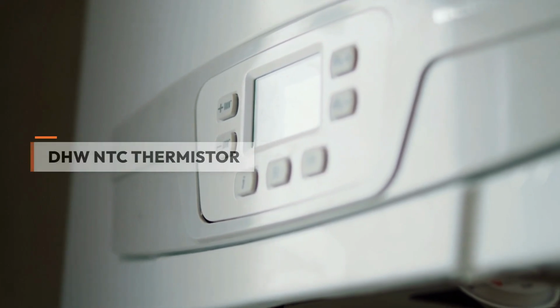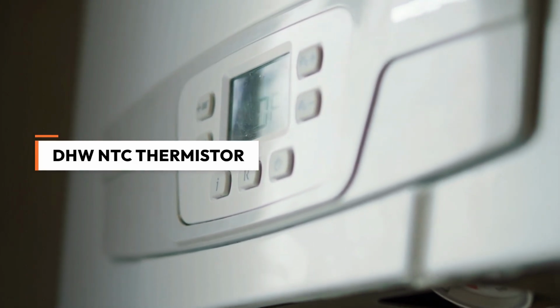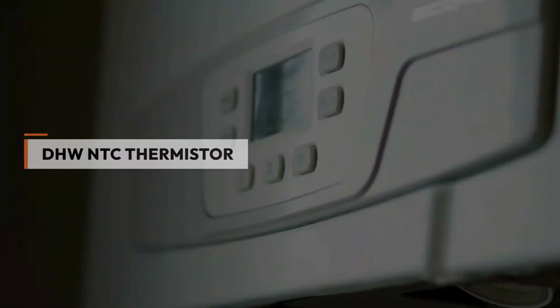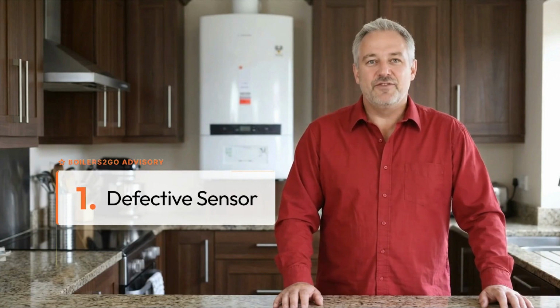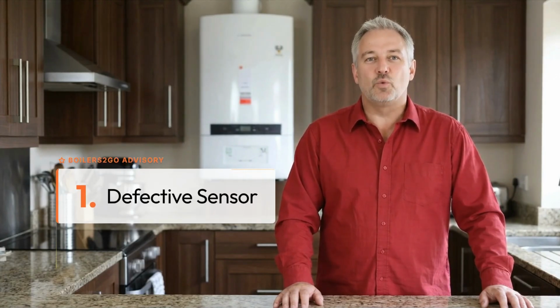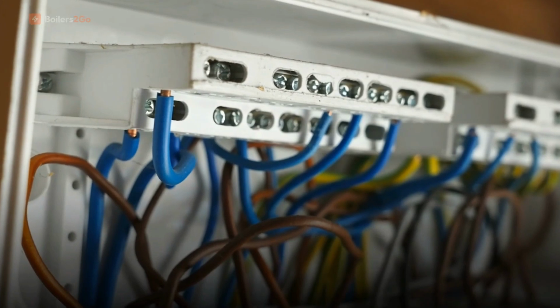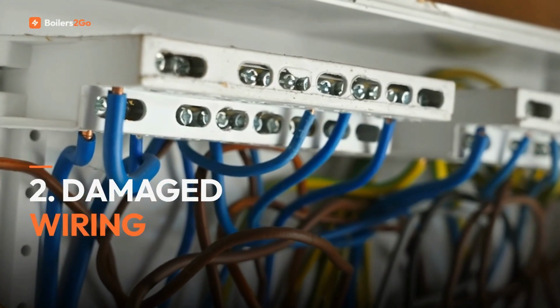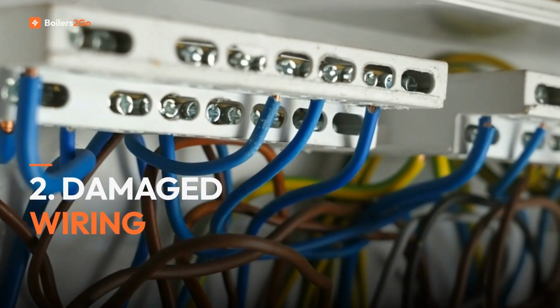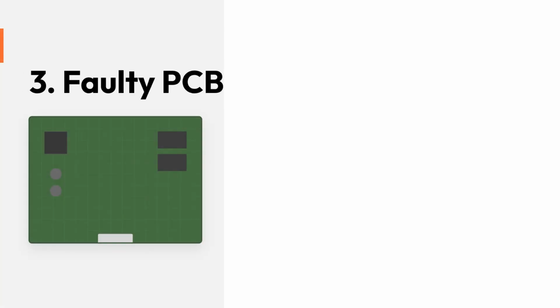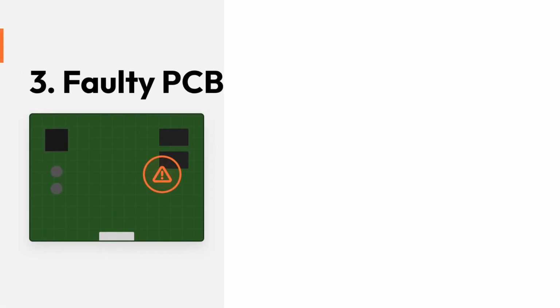It specifically points to a fault with the domestic hot water NTC thermistor sensor. The first main cause is a defective thermistor that can no longer monitor the water temperature accurately. Secondly, damaged or corroded wiring between the sensor and the control board can trigger the fault. Finally, a faulty printed circuit board, or PCB, might be failing to process the temperature signals.